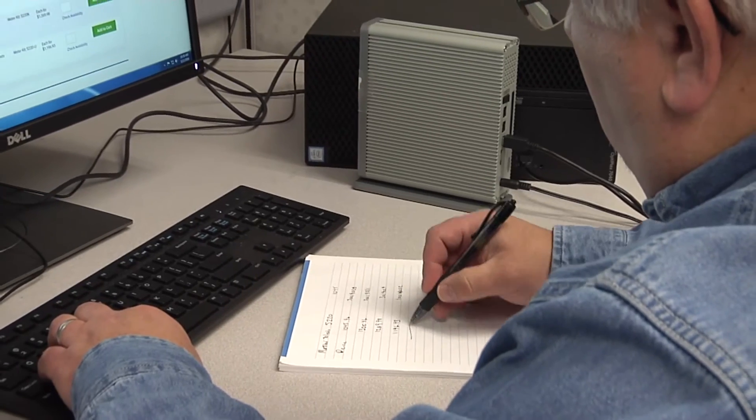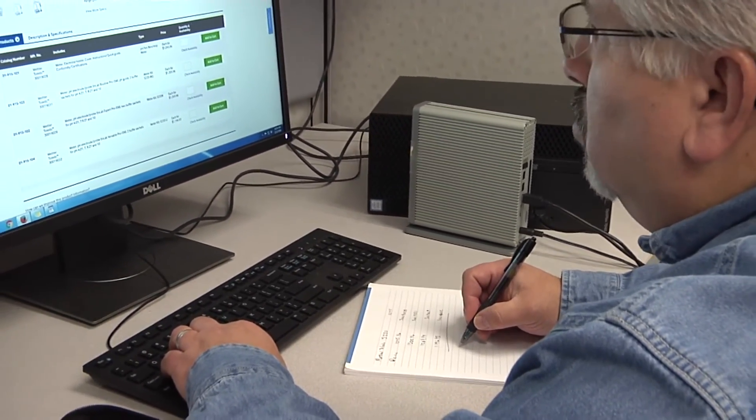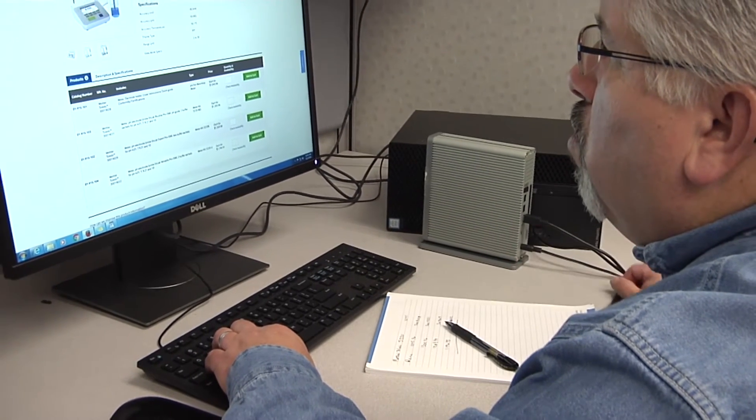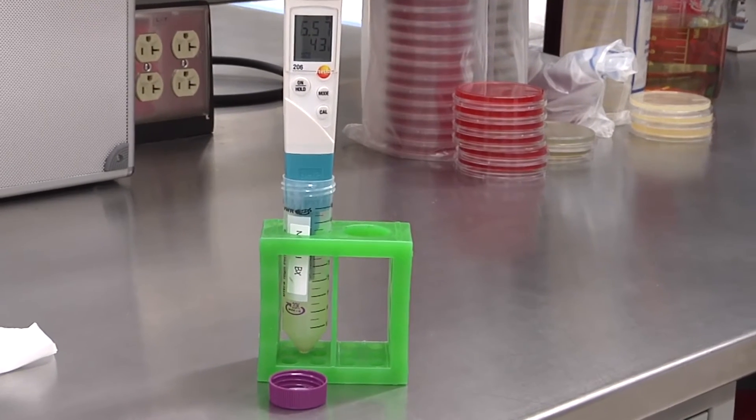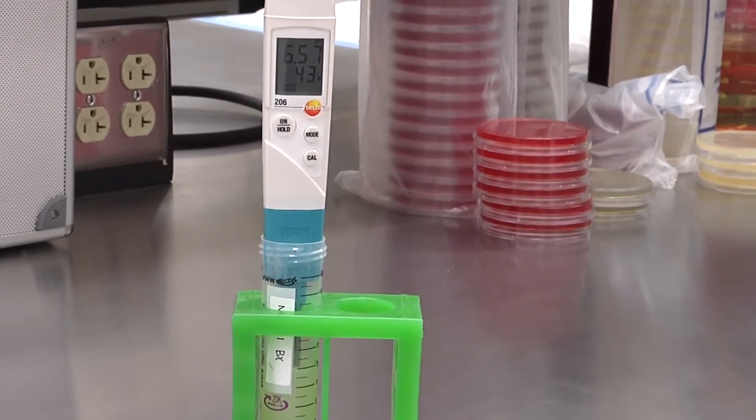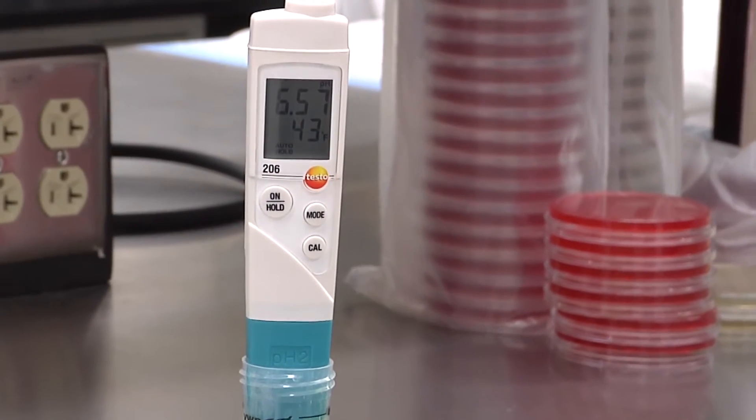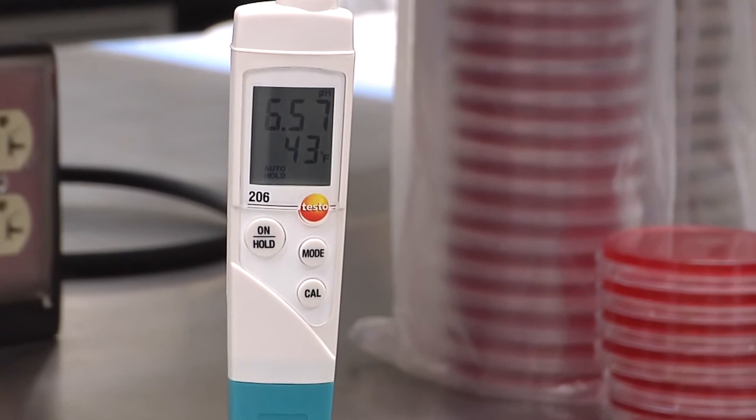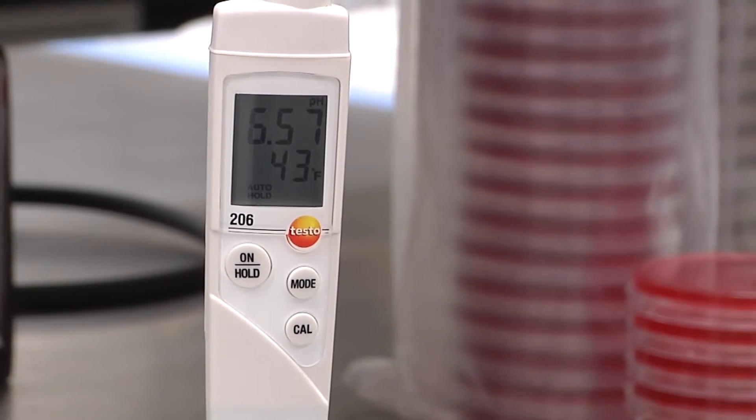First, you need to decide what level of financial flexibility your facility has to spend on a pH meter and electrode, and how portable the meter needs to be. If you are measuring cold samples, consider utilizing an electrode that calculates and compensates for differences in temperature. The meter chosen should measure in the hundredths place, and the accuracy should be at least plus or minus two hundredths.